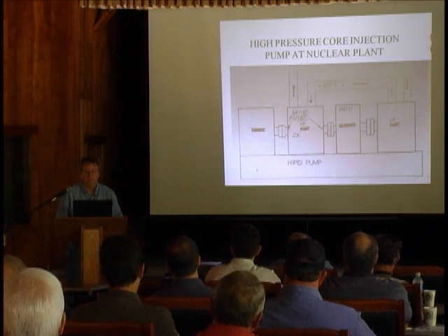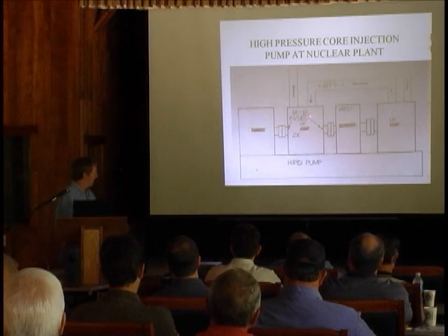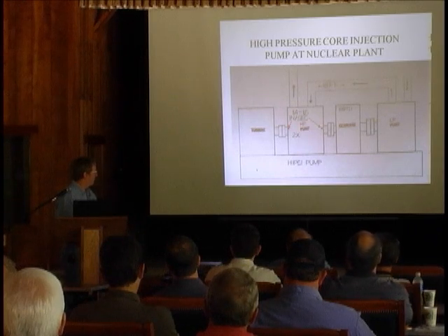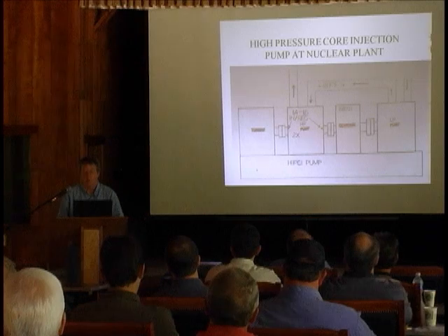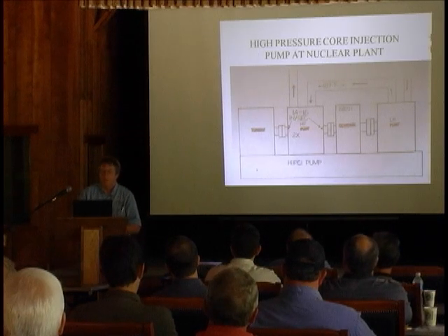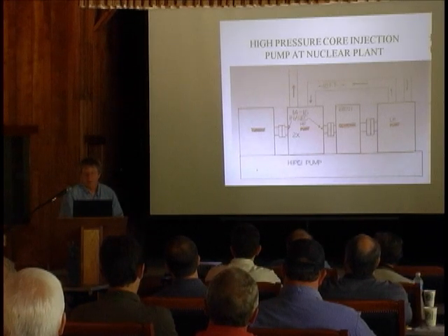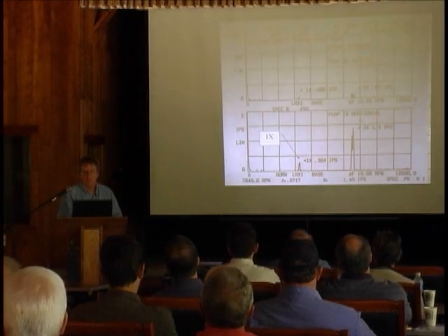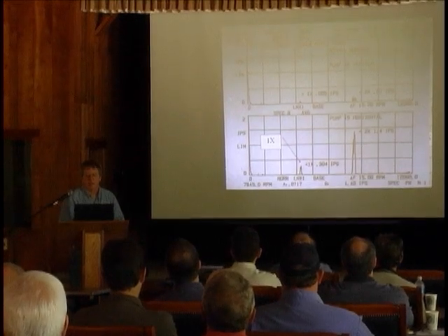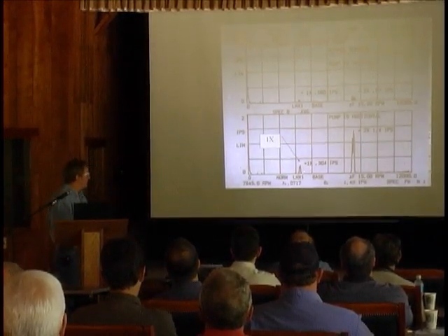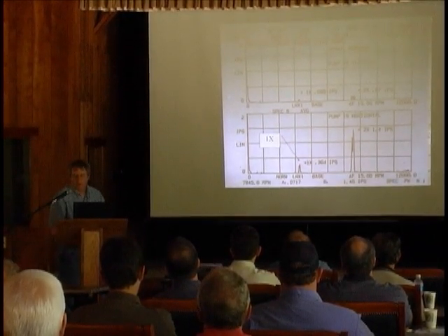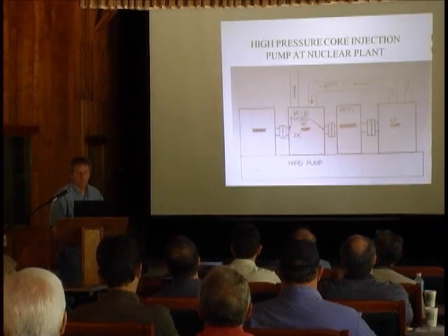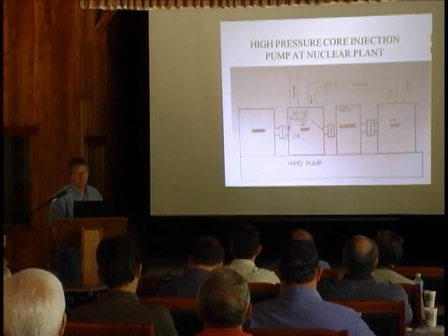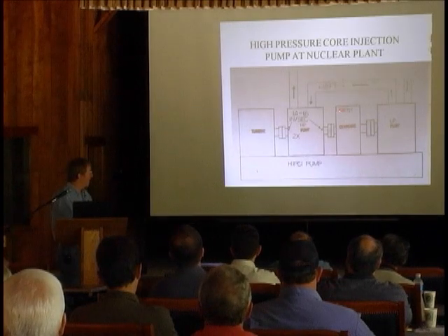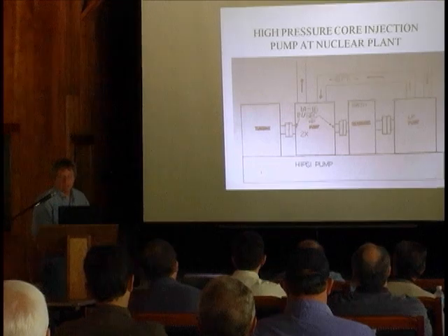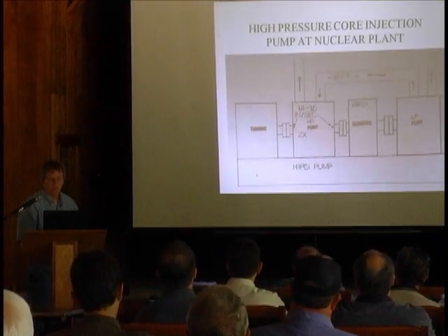But then they started doing stuff in velocity, and bingo, 1.4 to 1.6 inches per second on this pump, and that obviously got people all excited about it. So we took some readings on it, and the thing is, this frequency varies. This is a turbine drive, and speed wanders here and there a little bit. So that made things even worse. Also note this 1.987 to 1 reduction on the gearbox. That becomes very important as we move through this case history.